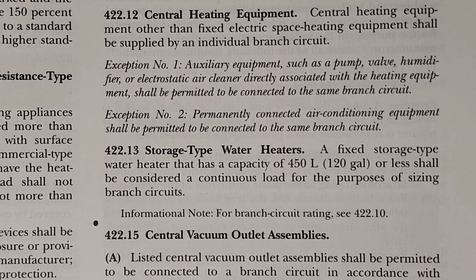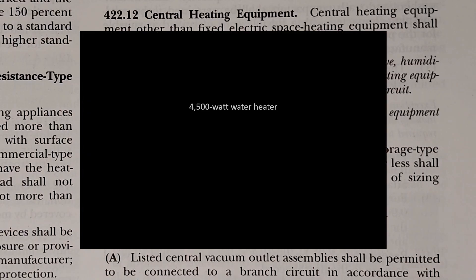Let's go ahead and take a real-world example. Let's imagine we have a 4,500 watt, 80-gallon tank and we're trying to figure out how to size the wire and the breaker. What we're going to do is take our 4,500 watts and divide it by our system voltage — in this case 240 volts. When we get that number, that's our starting value.